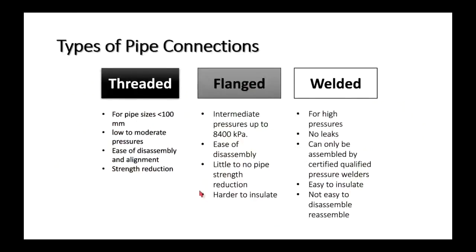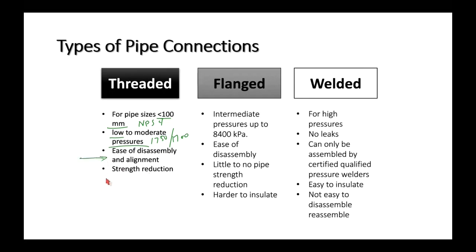Pipe connections: screwed connections are typically for NPS 4 and smaller, and for low to moderate pressures — below about 1700 kPa. The advantage is you can disassemble and reassemble without a welder. Because the pipe is threaded, you cut to a depth of H, so you must compensate for that strength reduction in your design.